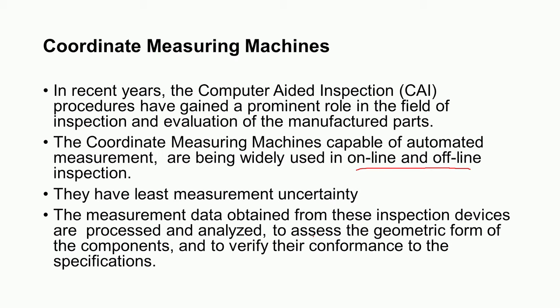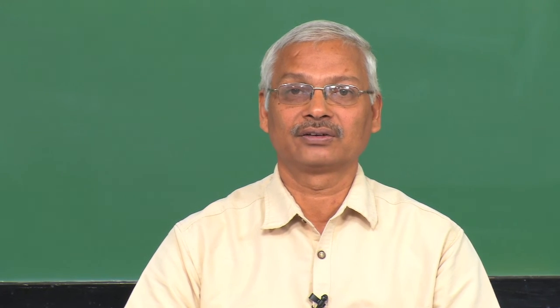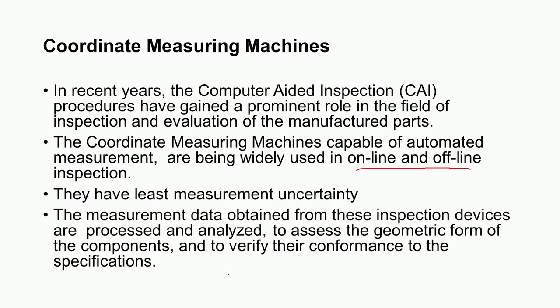There are probes attached to the CMMs — contact probes or non-contact probes such as laser spots. Depending on the length of the surface, a number of points are taken — for example, 6, 12, or 18 points. Those data points are given to software, which calculates the straightness or whatever feature is required, and then tells whether the component is acceptable or not.